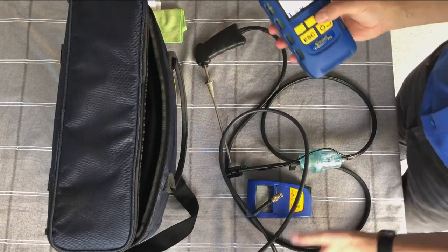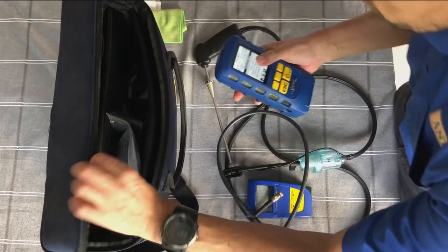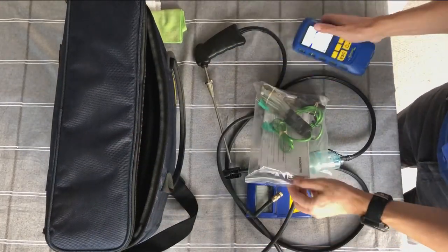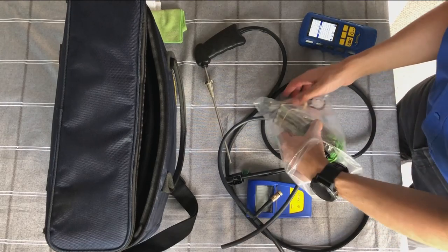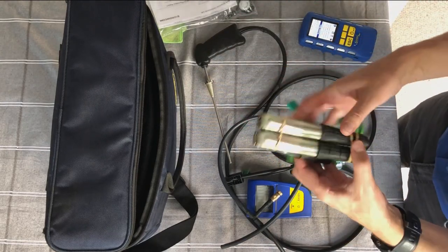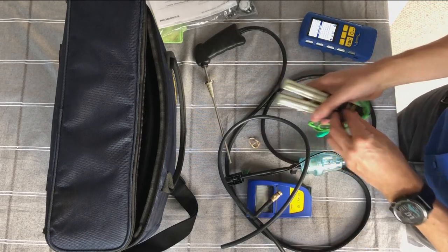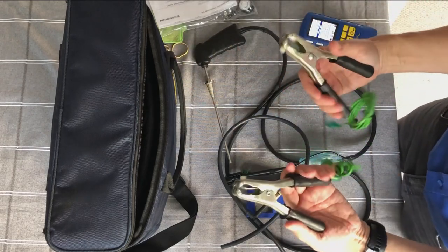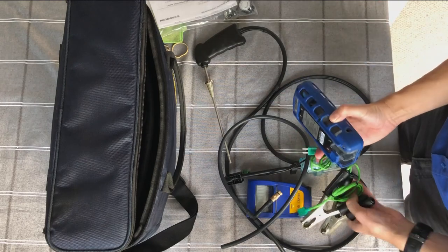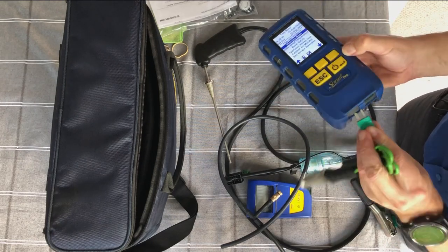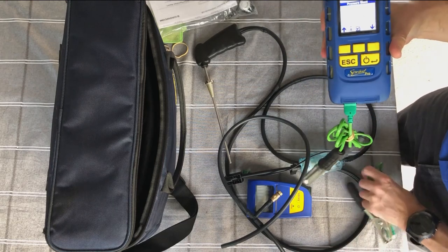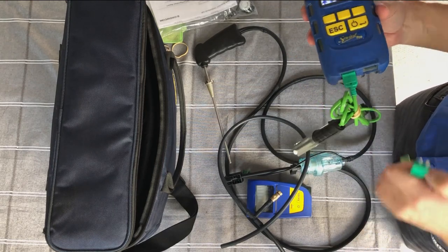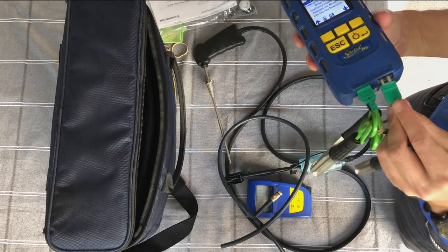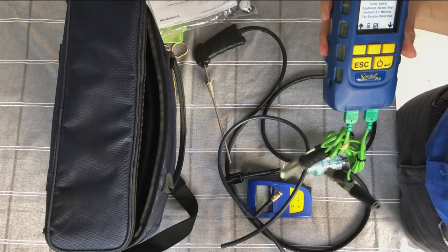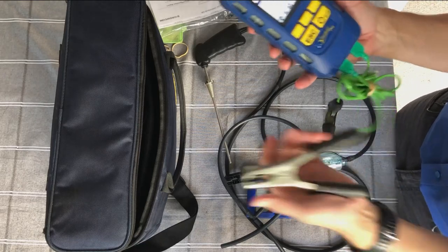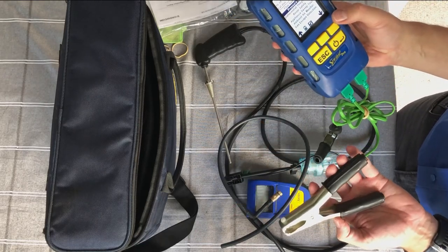Okay, differential temperatures. That's the pressure menu. If I go to the bag again, depending on your kit you can get some clamps provided. They come as a pair, and they go into the two sockets here. It doesn't matter which way around you connect them, it will work out which is positive and which is negative, your flow and return. The flow will always be the warmer of the two, so this will work out which is your flow and which is your return.